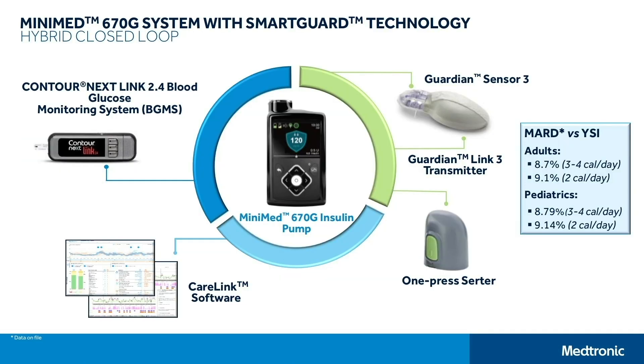At the center is our MiniMed 670G insulin pump with our SmartGuard auto mode algorithm. That algorithm accepts data from the Guardian Sensor 3 and then every five minutes goes through the calculations to determine how much basal insulin needs to be delivered. That sensor needs to be calibrated using our Contour Next Link 2.4 blood glucose meter. We have CareLink software that shows you the data retained within the pump so you can look at insulin delivery as well as glucose values. The Guardian Sensor 3 has a MARD — mean absolute relative difference — between sensor glucose data and a YSI by Yellow Springs instrument of 8.7 in adults and 8.79 in pediatrics, with three to four calibrations a day.